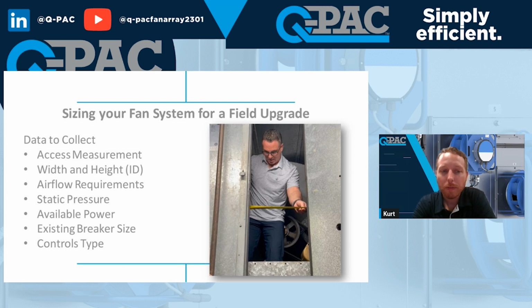As well as, will we have 575 volt for Canada in the future? Currently, that is not on our roadmap. In Canada, it seems that every building that has 575 also has 240, so we recommend doing 240. There's also a lot of transformer options where you can go from 575 down to 460 or 480. So not currently on our roadmap.